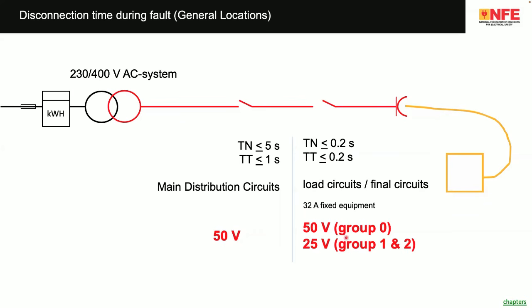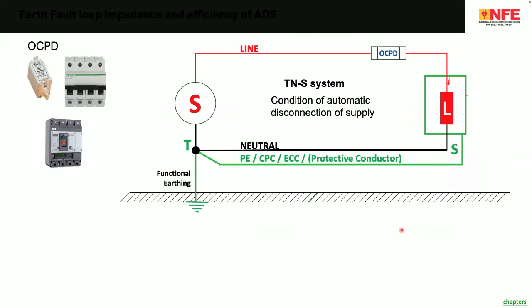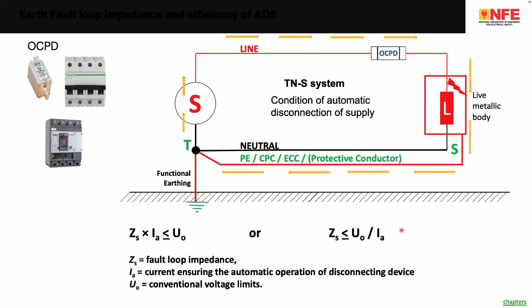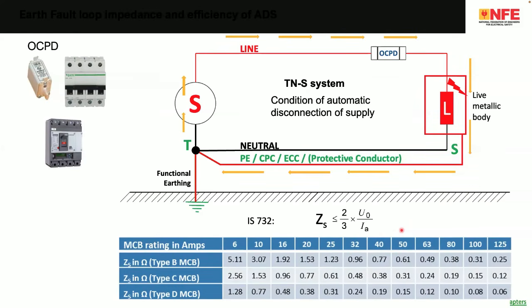Similarly, the touch voltage in each of the groups is very much specified. Fault loop impedance is one important subject which is catching up very fast in the country. It is not a new subject. It has existed since probably 1966. But in the new standards and regulation, this subject has been explained very well. Depending upon the type of the MCB, rating of the MCB, you have to keep the impedance of the circuit to a certain level. In the sense, when you have a DG, when you have a transformer, when your equipment is running from a UPS, the minimum requirement of the impedance you have to satisfy.